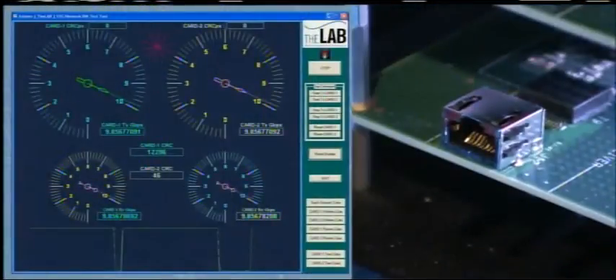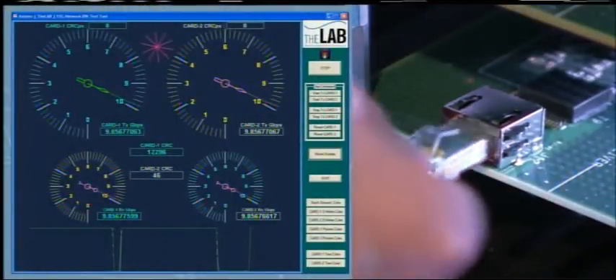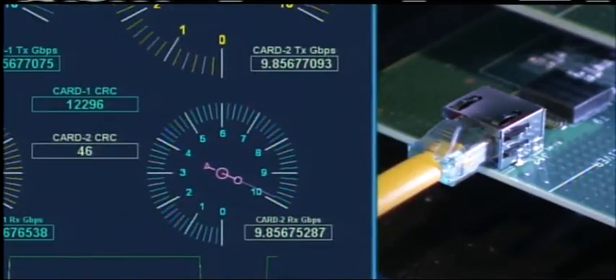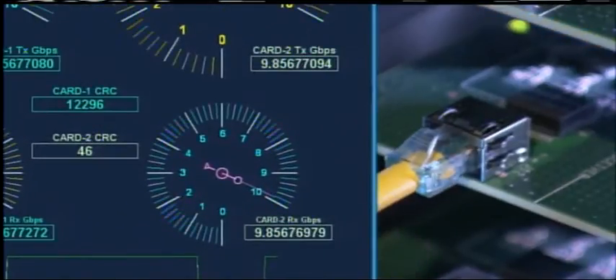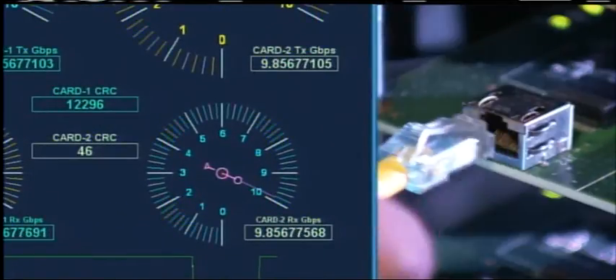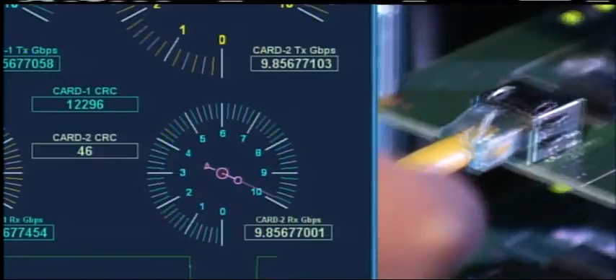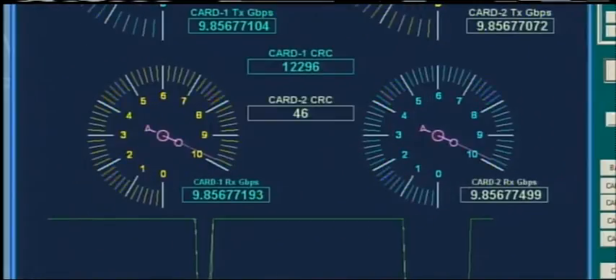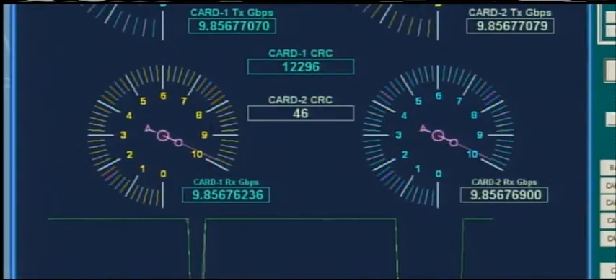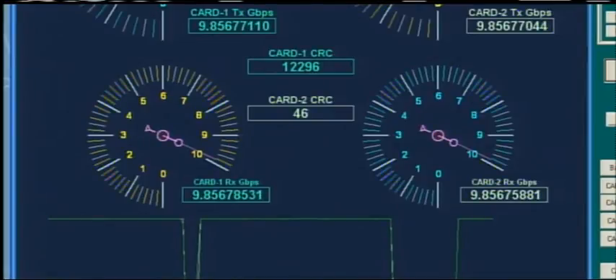Now we'll do the same test with 100-meter CAT 6A channels. Again, we'll start by connecting just one of the disturber channels, now two. We'll keep this up all the way through six disturbers. Not much change in throughput or error rate. Alien crosstalk is not affecting the test channel at all.